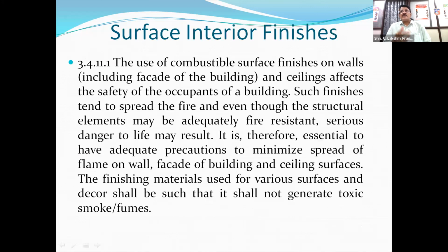Then the use of combustible surface finishes. This is also one of the important things when you are applying some finish on the interiors of the building. It will also act in spreading the flames if it is not of proper rating. There are different types of surface interior finishes which are rated with regard to fire safety, and that has to be complied with. Otherwise, it will result in quick spread of flame from one place to another because of the surface interior finishes. We have to take care especially when you are putting a lot of interiors in the building without any regard to their fire behavior.